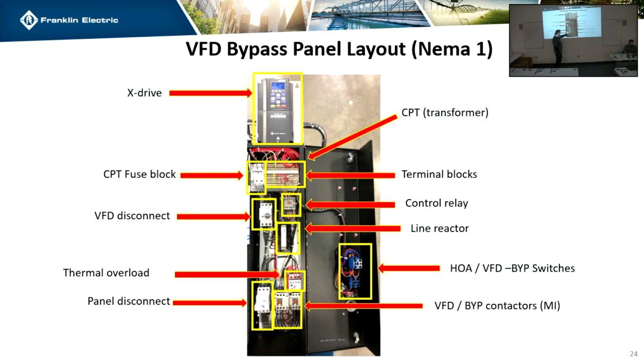And then we have our two contactors. Down here you will have a sticker. You can't really see it in this picture, but there's a white sticker that says input, and there's another white sticker that will say motor, and it'll tell you which one to go into. For the bypass panels, you're going to double up on one set of wires. There's jumpers that go between the two contactors. You just feed the motor into one of them.